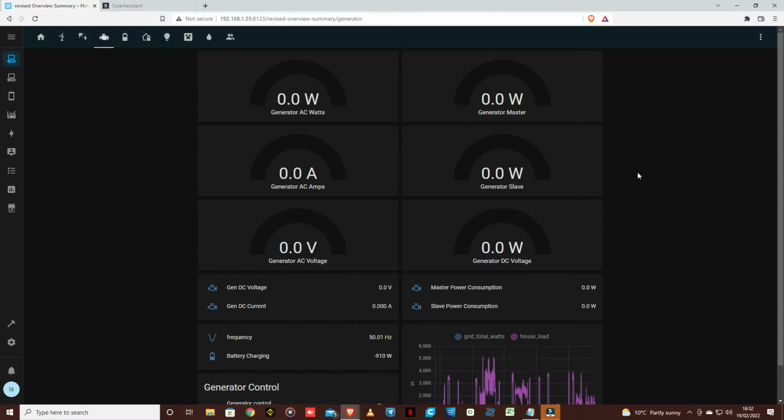With SMA's equipment, you find 99% of the problems actually come back to, if you're off grid, the generator. You've got physical problems with the generator, obviously, but more than anything you've got frequency problems. If your generator's frequency is too high, it's running too fast, because the generator speed is directly linked to frequency. So if the speed is too fast, your frequency will be higher. Let's call it 50 hertz, it will be 50, 51, 52, etc. At a certain point, it won't work anymore connected to your own mini grid. It'll just disconnect it.